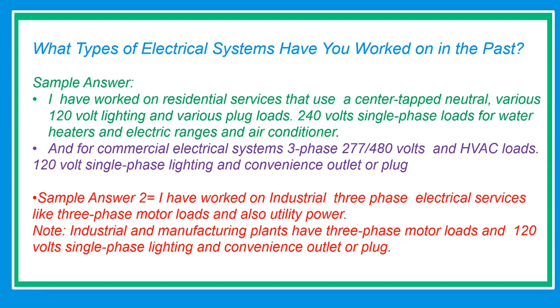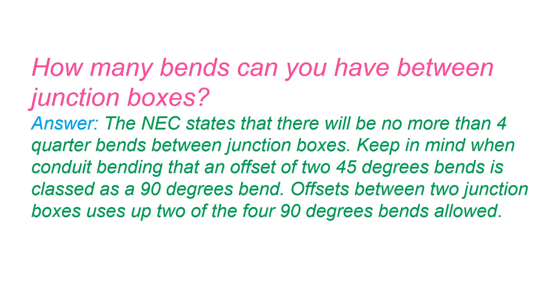How many bends can you have between junction boxes? Answer: the NEC, or National Electrical Code, states there will be no more than 4 bends between junction boxes. Keep in mind, when conduit bending, an offset of 2 is classed as a 90 degree bend. An offset between two junction boxes uses up two of the four 90 degree bends allowed.